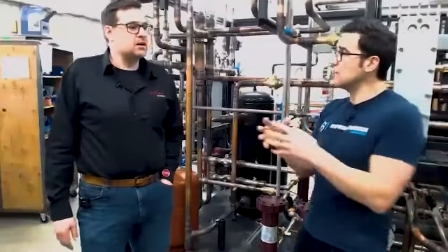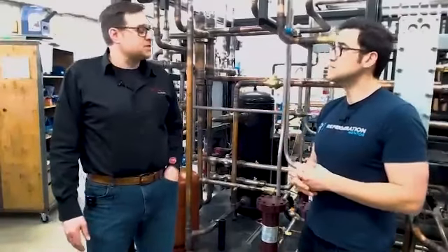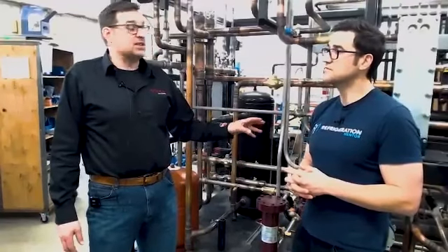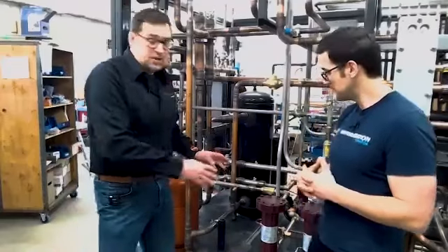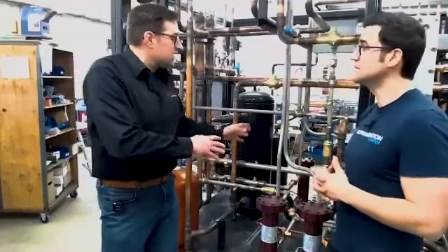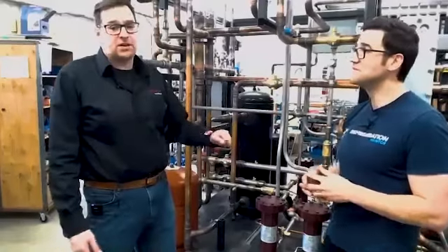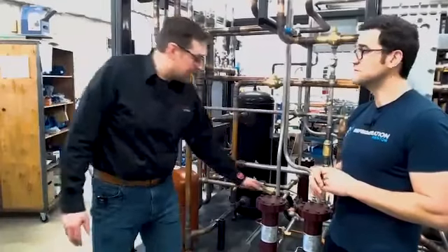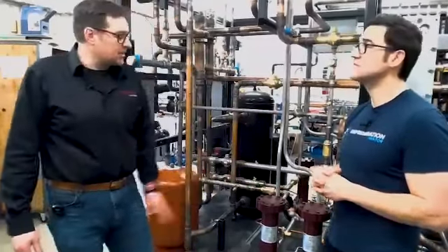Is that why you use these two different circuits, based on the size of the system? Yeah, absolutely. The application behind us is a mix between refrigeration and HVAC, an HVAC flooded system with about 1 million BTUs going out. We use free cooling throughout the winter months, so there's a good 6 months where the HVAC application isn't even running. We have to properly pump that system out and leave it idle. We're going to go through how we achieve that and how we avoid return gas migrating back into the oil separators, which is a common phenomenon that occurs with CO2.